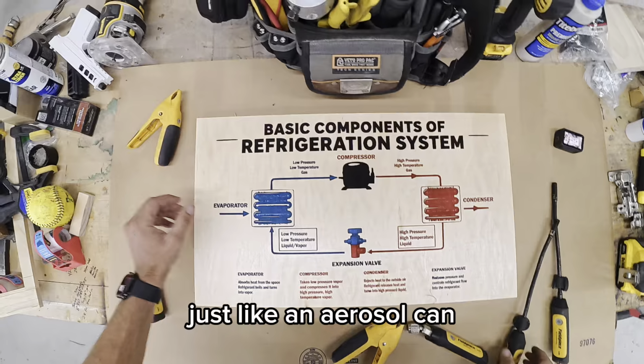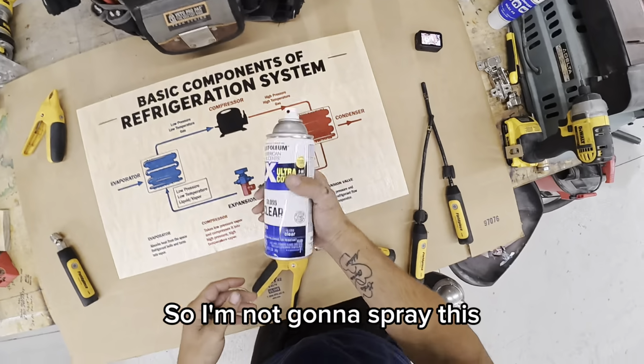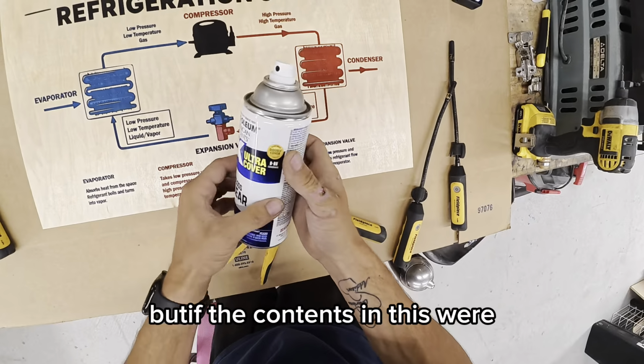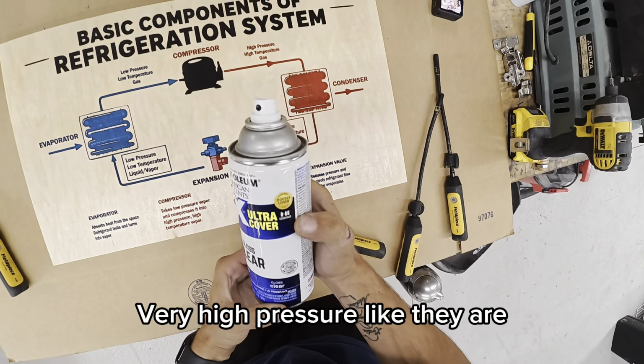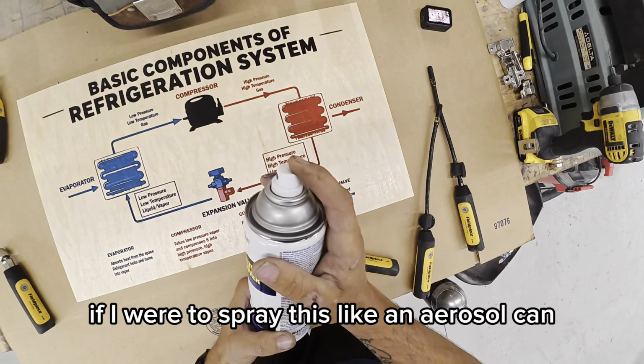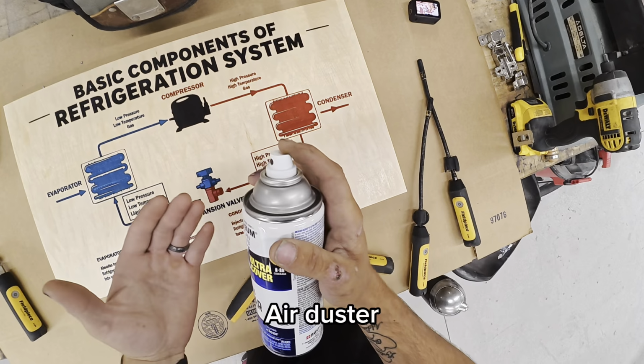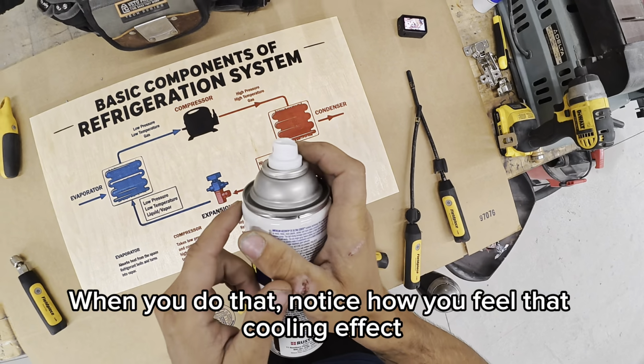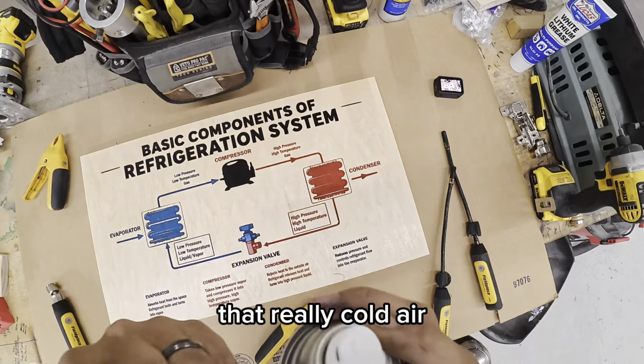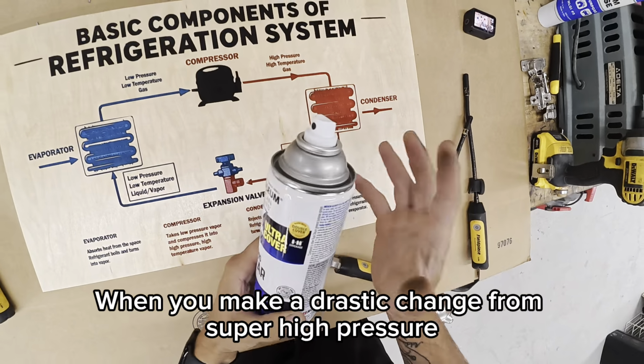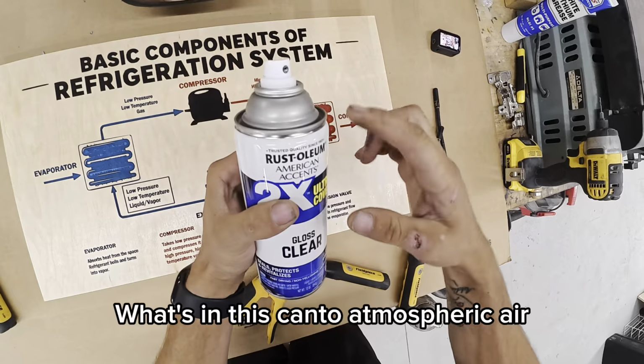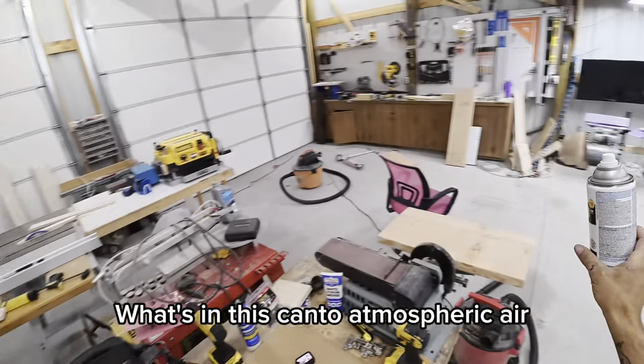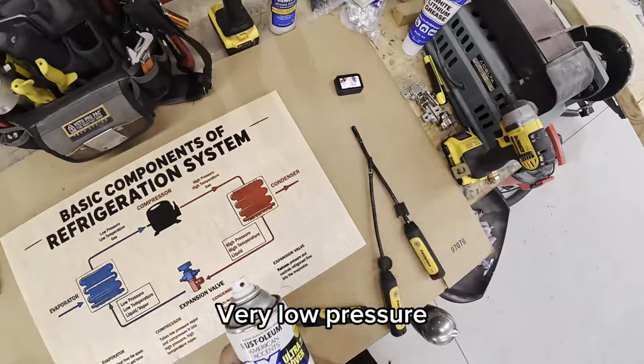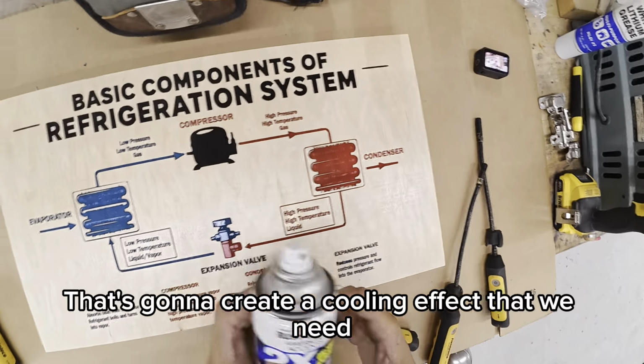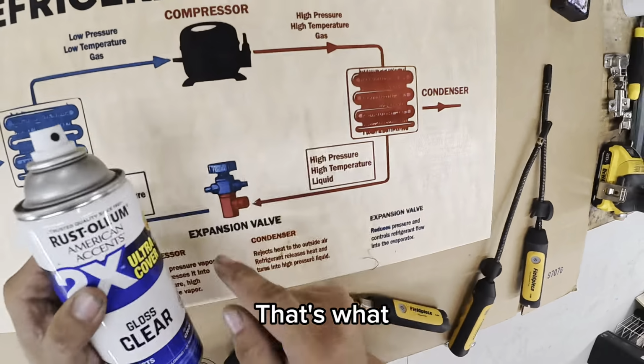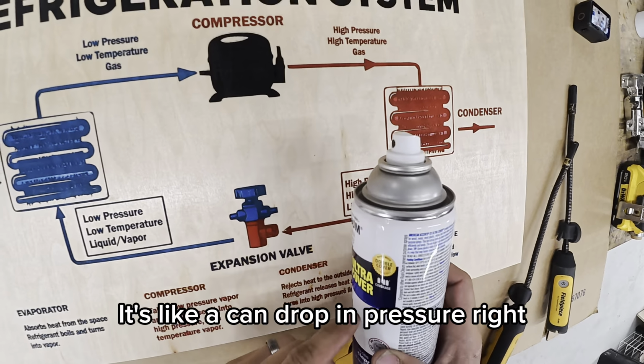Just like an aerosol can. So I'm not going to spray this, but if the contents in this were very high pressure like they are, if I were to spray this like an aerosol can, air duster, when you do that, notice how you feel that cooling effect, that really cold air. When you make a drastic change from super high pressure, what's in this can, to atmospheric air, what's around us, which is very low pressure, that's going to create a cooling effect that we need. So basically, that's what this expansion valve is. It's like a can dropping pressure, right?